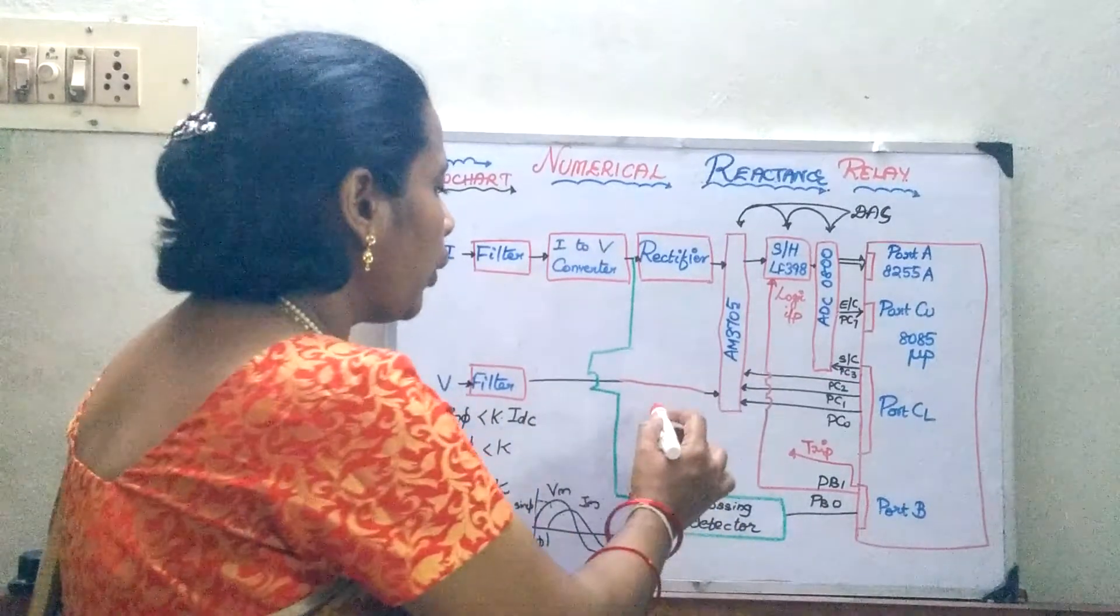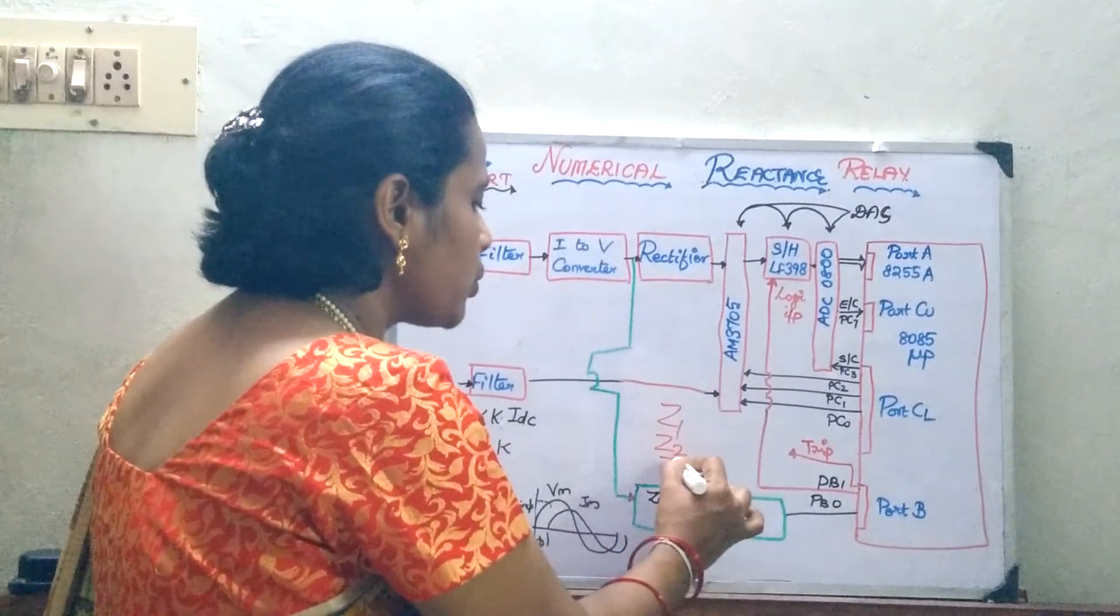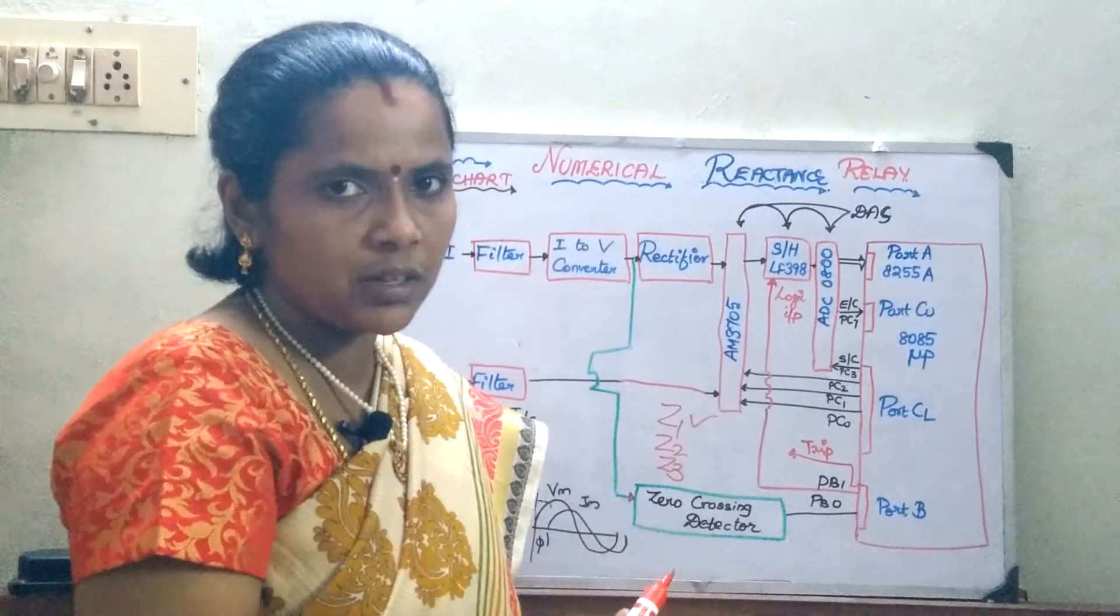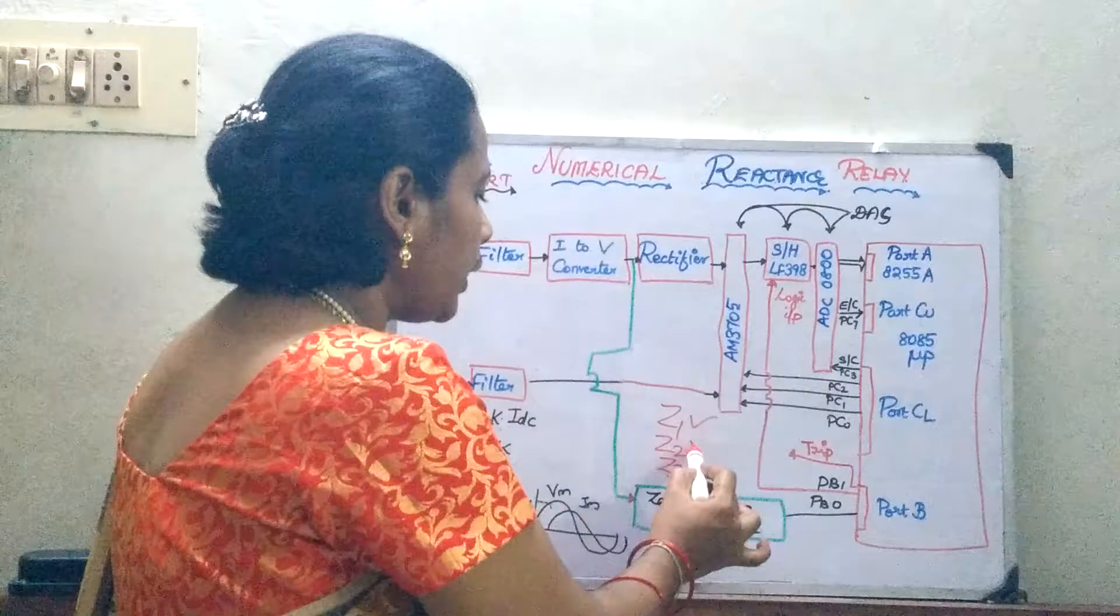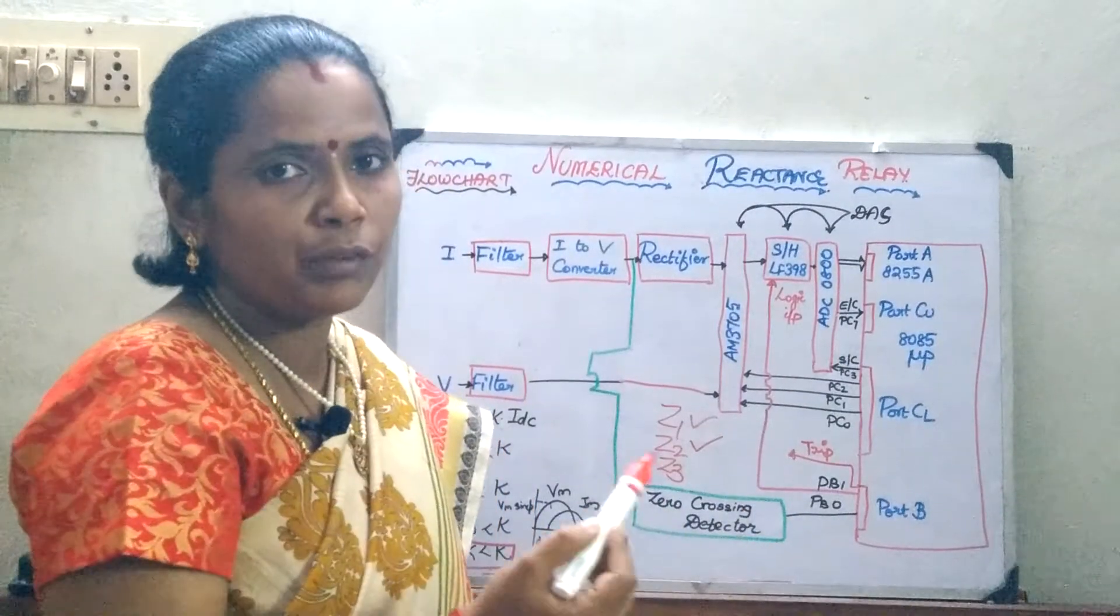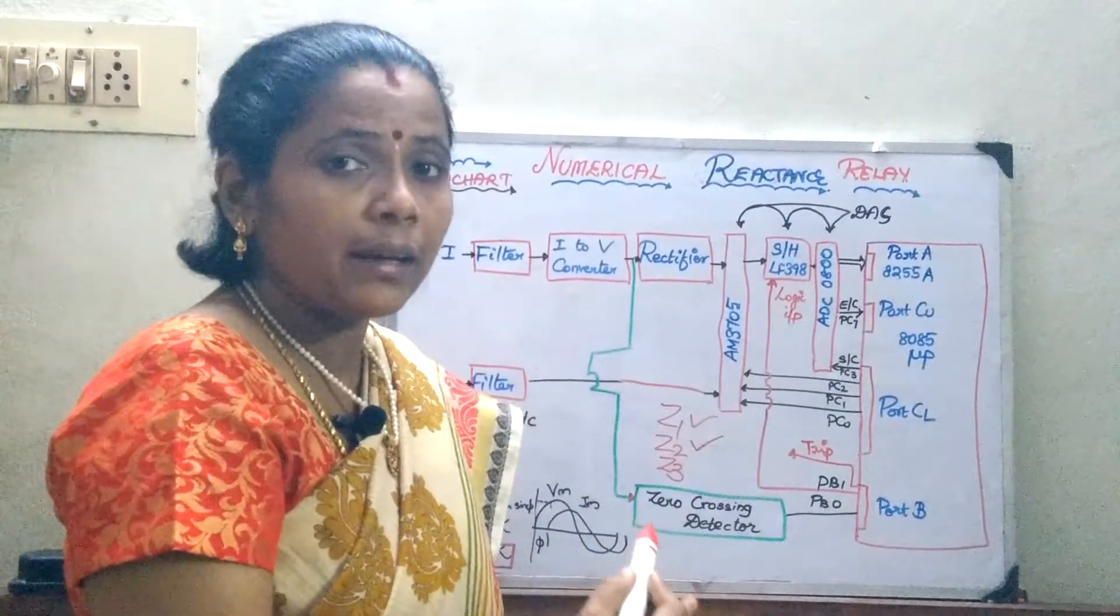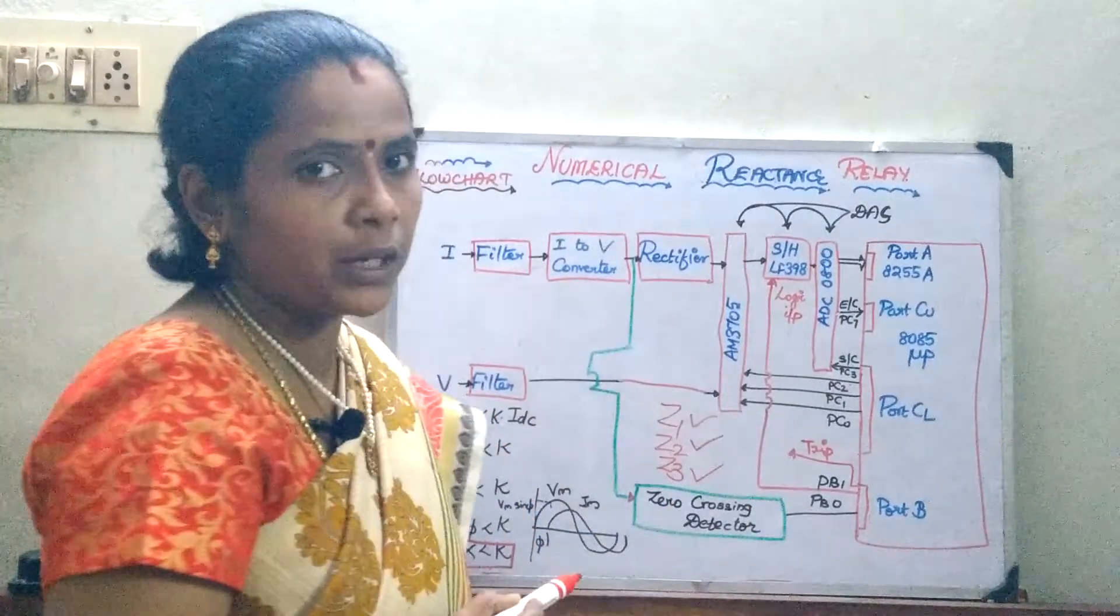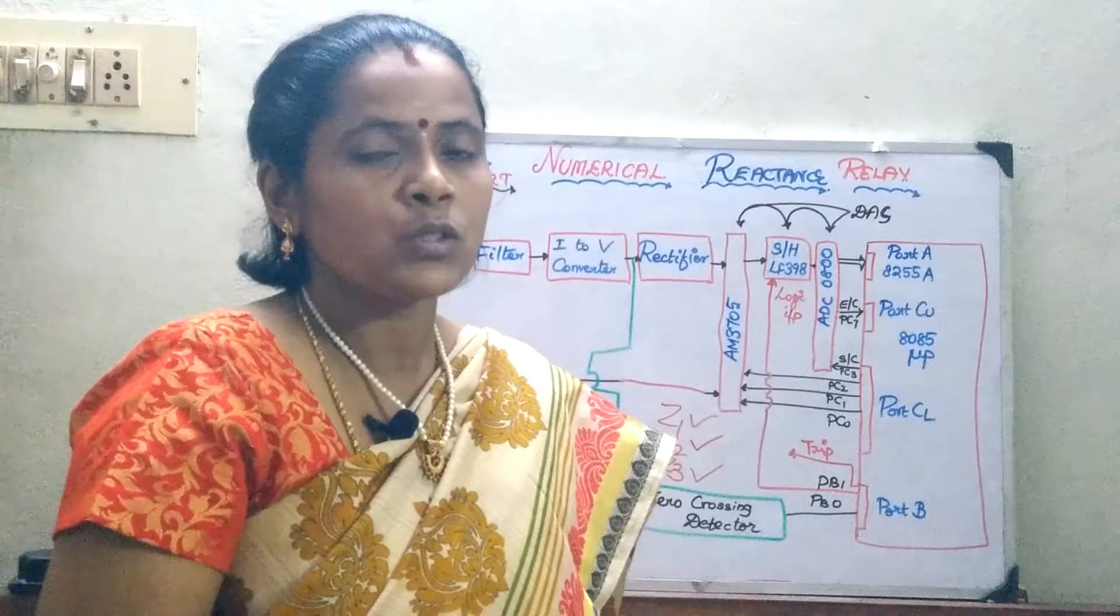Of course, the same concept, whenever I am going to take the three zones, zone 1, zone 2, zone 3, so this zone 1 will act immediately going in for your instantaneous protection. This will operate after a predetermined delay going in for your second zone protection and after a great delay, the third relay will act upon because it is going to provide the protection for the adjacent section.